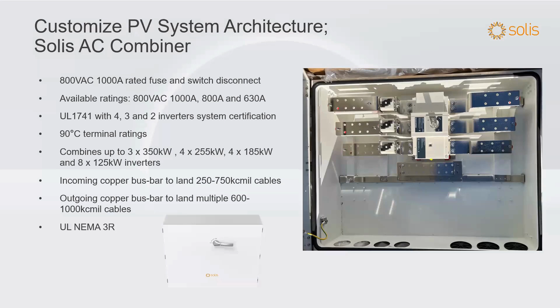Now, another thing I wanted to mention concerning the flexibility of the PV string inverter platform is the capability to bundle them, to use a term from the telecommunications industry. This is our AC combiner, a Solis product. This AC combiner has a 1000 amp rated fuse switch on the front, takes fuses - 800 at 1000 amp, or 800 amp at 630. There's a whole bunch of different varieties. I'm going to show you a piece here. You can really combine a bunch of inverters - 2, 3, 4 inverters - all together into this AC combiner.